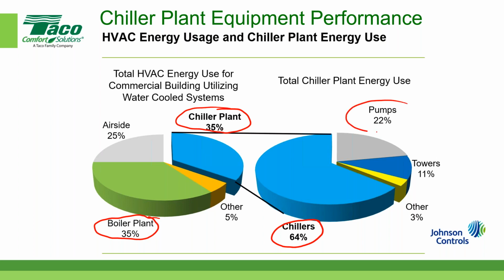The pumps are about 22%, and the cooling towers, if it's a water-cooled system. We're going to talk about both air-cooled and water-cooled for a couple of minutes, but we're going to focus our attention mostly on water-cooled because that's where the majority of chiller plants are these days. Well, I shouldn't say the majority. What I should say is that in many cases, chiller plants are water-cooled because they can have a significant energy-saving component, and we'll talk about that in a minute.